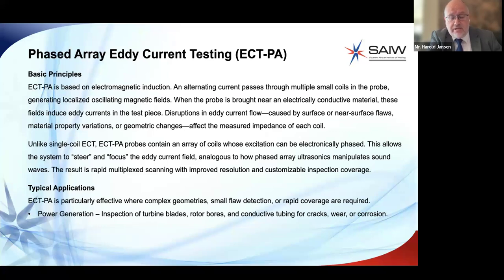Unlike single coil eddy current, phased array eddy current probes contain an array of coils whose excitation can be electronically phased. This allows the system to steer and focus the eddy current field, very similar to phased array ultrasonics. The result is rapid multiplex scanning with improved resolution and customizable inspection coverage, which is typically used to inspect turbine blades in power generation, rotor bores, and conductive tubing for cracks, wear, or corrosion.